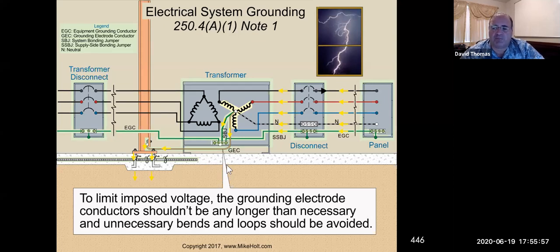So length is another important point, because the longer the length, the more resistance. You remember that rule that current, or electrons, try to find the path of least resistance back to the source. That could mean that an alternate pathway, which might be an unsafe pathway, may be the choice of the electron, to take that unwanted pathway. So our whole thing is to create controlled pathways for electrons. We're always trying to control the path that the electrons take, whether during short circuit, ground fault, or overload, so that they flow where we want.